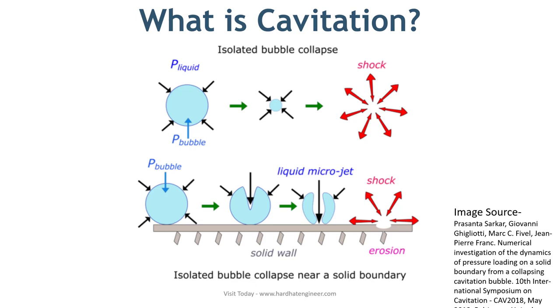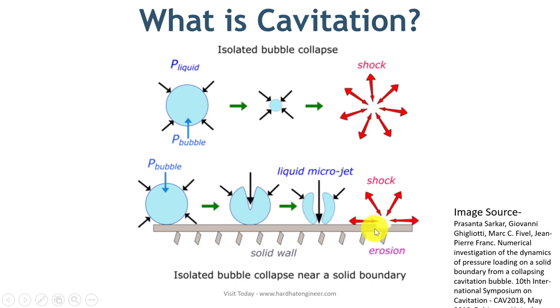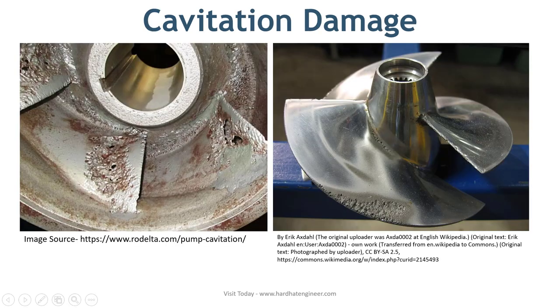There are many reasons for vapor bubble creation, which I will explain in a minute. First, look at the image shown here — it shows collapsing of bubbles near the surface and away from the surface. When a vapor bubble collapses far from the surface, it creates a shock wave inside the liquid. When it collapses near the surface, the pressure jet hits the surface with pressure in the range of 10,000 to 15,000 psi, creating pits and eroding the surface.